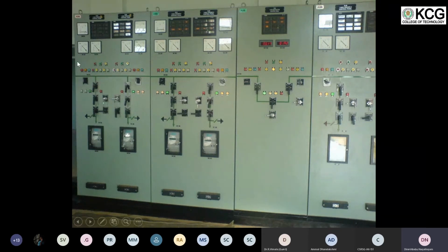Then you have the metering screens, where you can see whether voltage is available, current is available, power flow is available or not. All this information you can see. And the annunciation panel. This is the annunciator window. This gives information to the user about what is happening in the system. If a relay trips, there is an annunciation. If the breaker is operated, there is an annunciation. If your system is healthy, that is also an annunciation. Depending on the system condition, the color also may change. Maybe orange color, red for trip, green for healthy. Like that, you can have different color indications. You also have an energy meter, which is shown in the bottom.